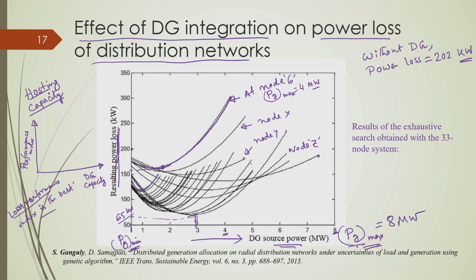So what you can do is see these characteristics: performance index is decreasing with the increase of DG capacity, and there will exist a point where we have the lowest performance index, which is the best value. Corresponding to that we have the DG capacity, which you can consider as the optimum DG capacity. According to this hosting capacity concept, it is the capacity of DG which can be integrated into a distribution network without deteriorating the performance of the network.